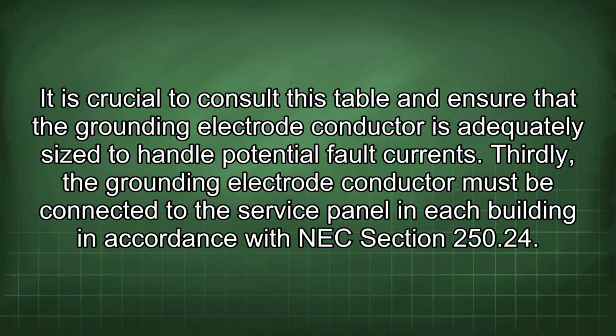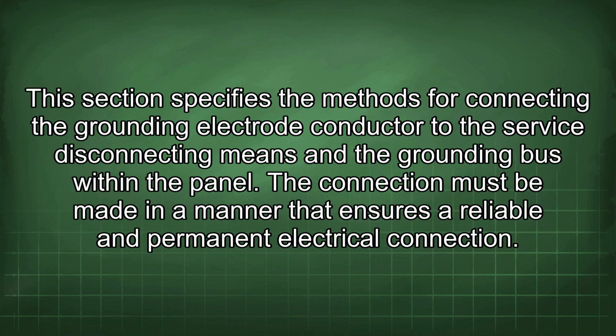potential fault currents. Thirdly, the grounding electrode conductor must be connected to the service panel in each building in accordance with NEC Section 250.24. This section specifies the methods for connecting the grounding electrode conductor to the service disconnecting means and the grounding bus within the panel. The connection must be made in a manner that ensures a reliable and permanent electrical connection.